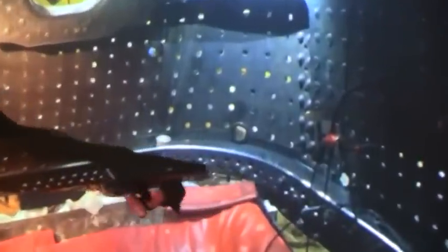It all has to be cut out. All of those stay-bolts had to be removed. And while we're at it, we're going to replace this. This is the lower part known as the mud ring. Each one of those is a hot rivet, nearly 10 inches long, almost 1 inch in diameter.